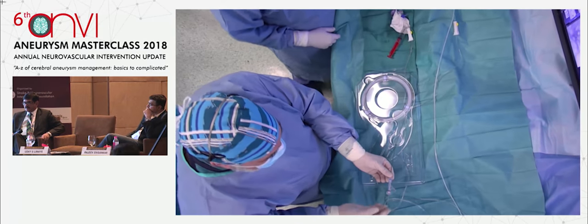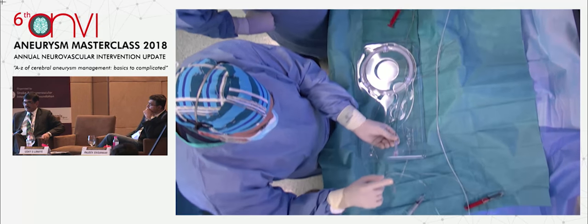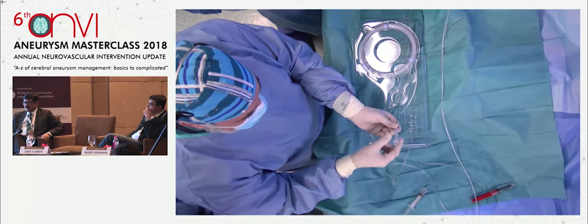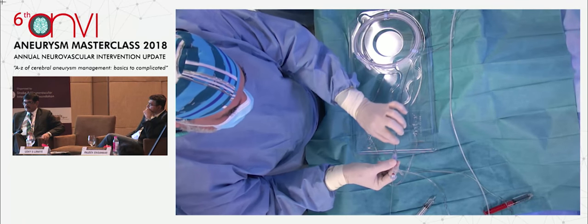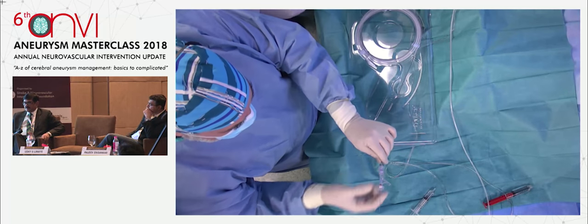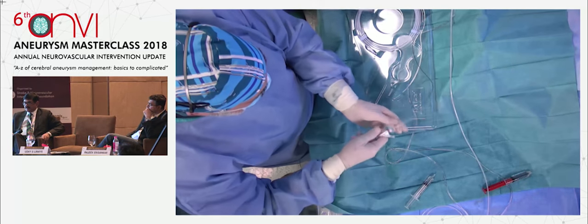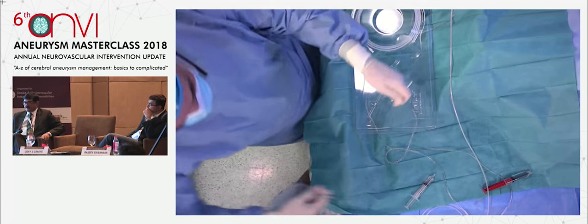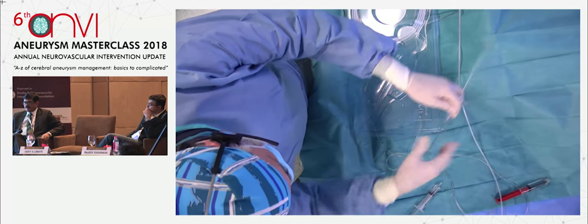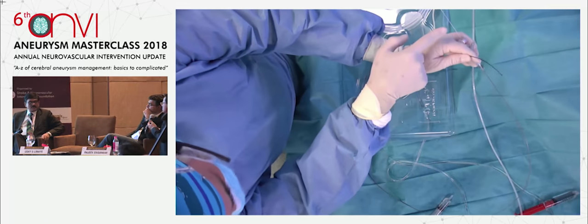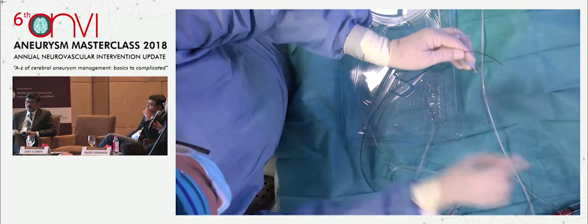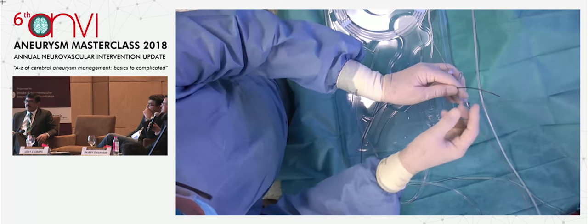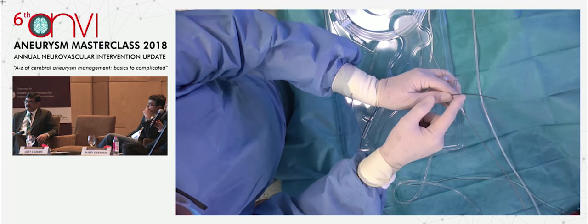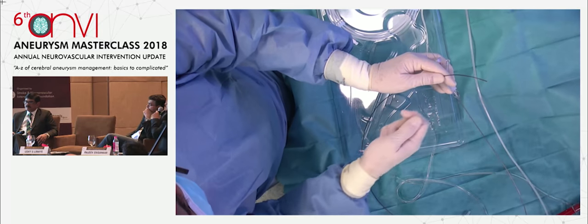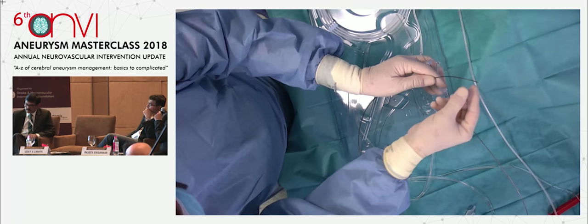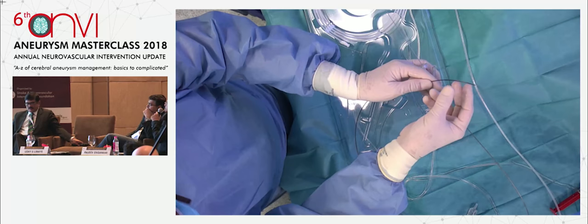Yeah. This is the stent system. You can see we zoom there? This part is the pusher. This part is the Y valve, and this is a simple catheter. And the stent is inside. In between, it is. Can we zoom the image a little bit here? Yeah. Great. So you see, this is a two-axial system. You get a pusher inside, an external catheter, and the stent is here in the middle. Linked in between the pusher and the external catheter. When we pull back the catheter, the pusher stays in place, and the stent will open.